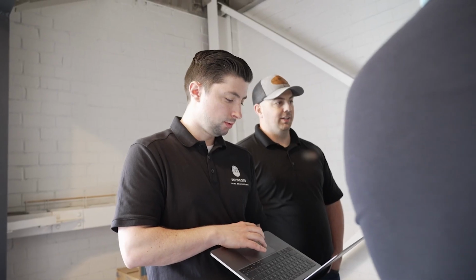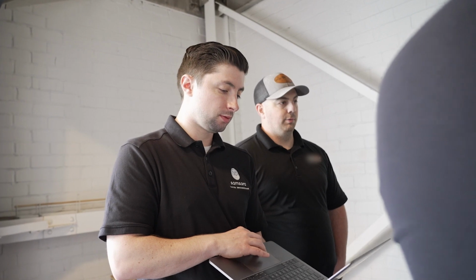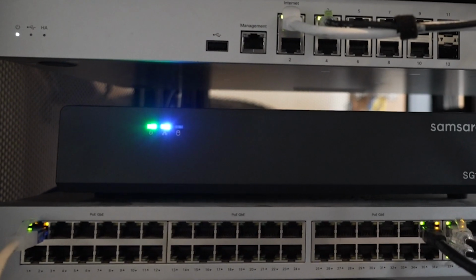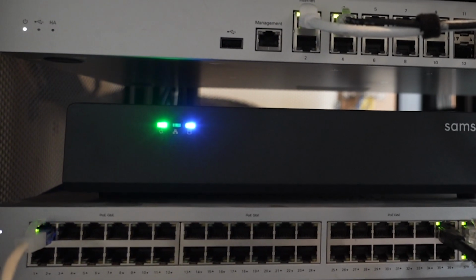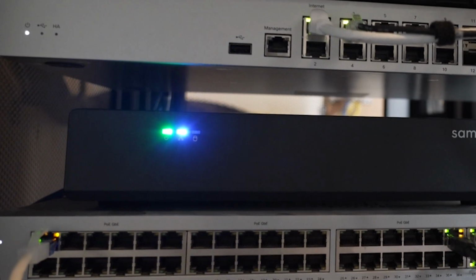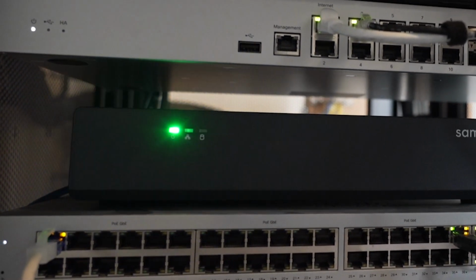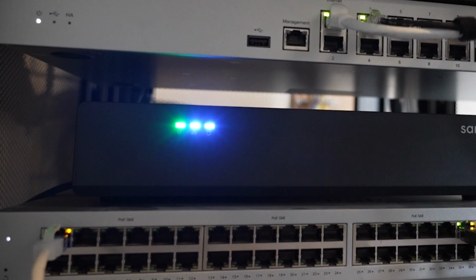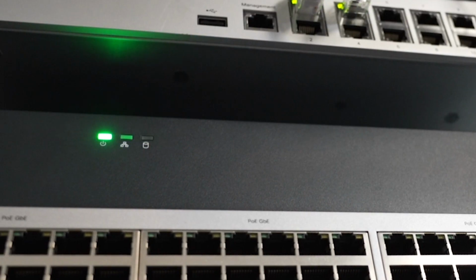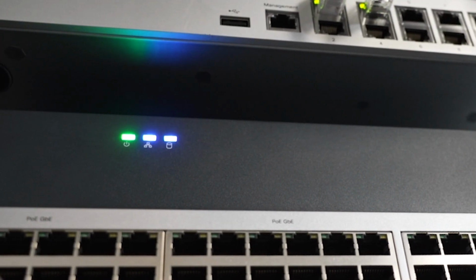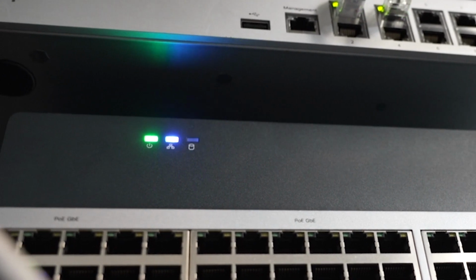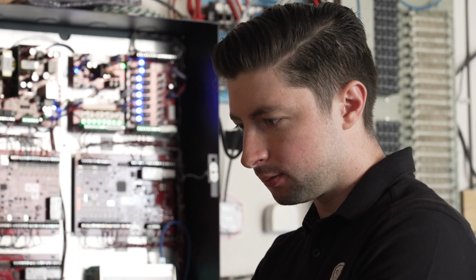Now, verify your site gateway is connected to both the network and power, indicated by the status lights on the front of the gateway. If the leftmost light is red, this means that the device is plugged in but not yet powered on. If the light is green, this confirms you have powered on the gateway. You will also want to ensure the middle light is flashing blue to indicate that there is network activity. Now you're ready to activate your site gateway in the cloud.